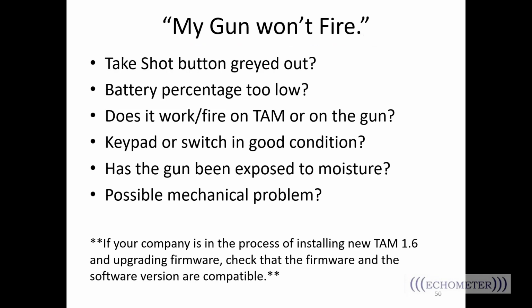All right, so the next common problem that we see: my gun won't fire. We've got a little troubleshooting list here. Is the fire button continuing to flash and never coming full on? Is the take shot button remaining grayed out? That could be an indication that you've got an older solenoid, or that your solenoid is going out or has gone out. And sometimes you can see that about to occur.